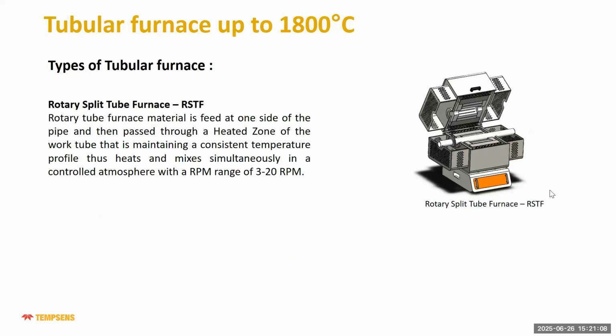Then we also have a rotary split tube furnace. So if you want to rotate the tube furnace at some RPM, at slow speed or high speed, we can do it in a split type tube furnace, the rotary split type tube furnace. And it can give you a constant heating zone, and the RPM range can be 3 to 20 revolutions per minute by a motorized system.